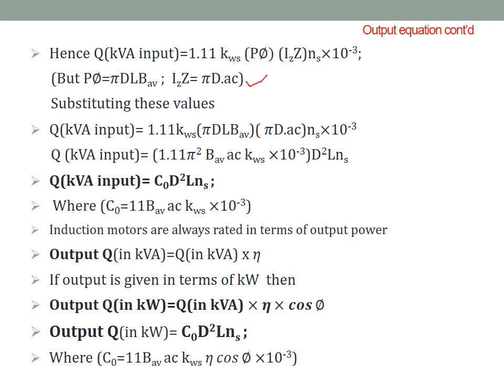Substituting these values: Q KVA input = 1.11·Kw·(π·D·L·B_avg)·(π·D·AC)·Ns × 10⁻³ = 1.11·π²·B_avg·AC·Kw × 10⁻³ · D²·L·Ns. So finally, Q KVA input = C₀·D²·L·Ns, where C₀ = 11·B_avg·AC·Kw × 10⁻³ (since 1.11·π² ≈ 11). This has also been discussed in DC machines.